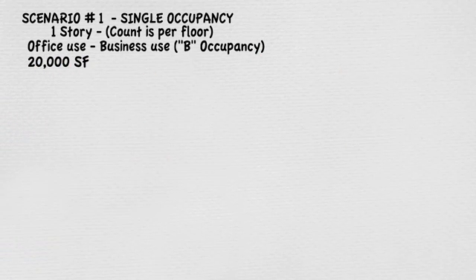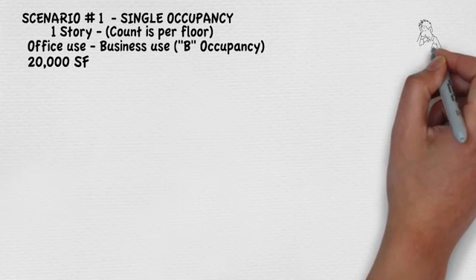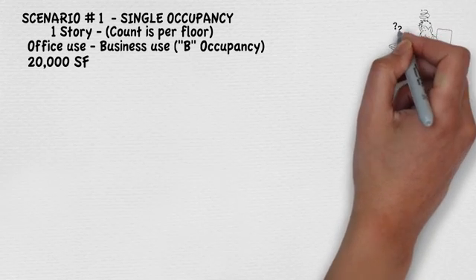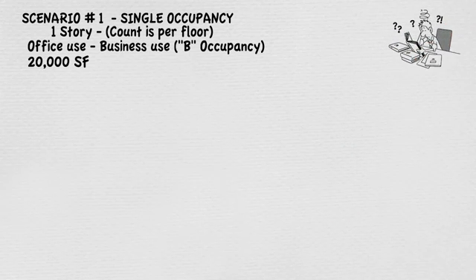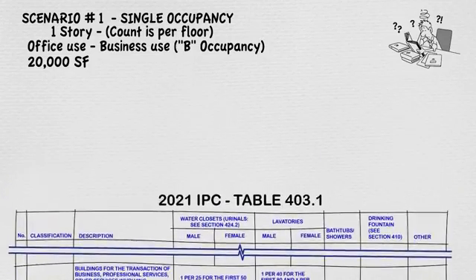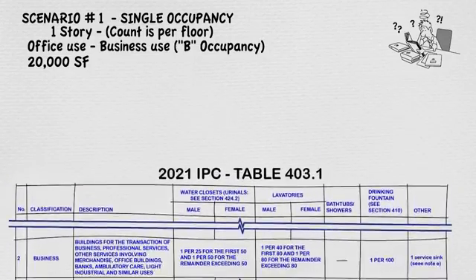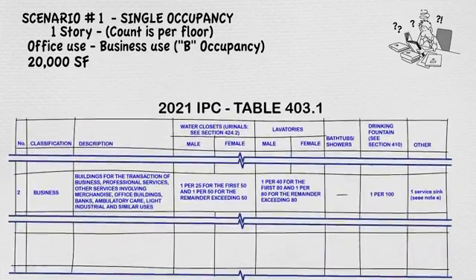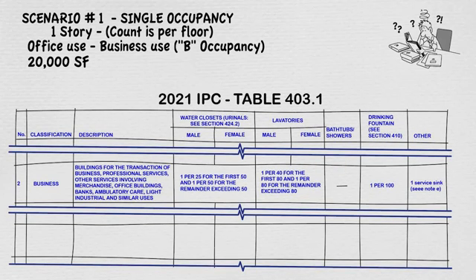The office is 20,000 square feet. We need to figure out the required plumbing fixture count. You have to go to the International Plumbing Code to do this. Section 403 is the section we are interested in. There is a chart that shows the requirements for the number of plumbing fixtures required, and it is based on occupancy groups and occupancy loads.